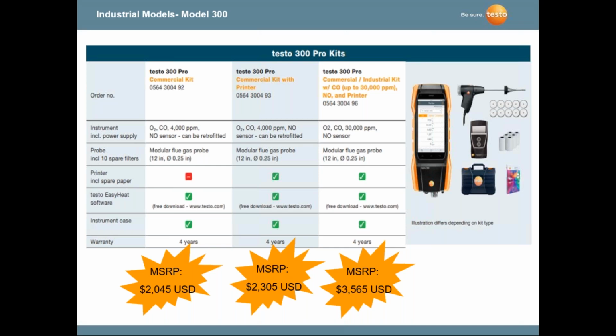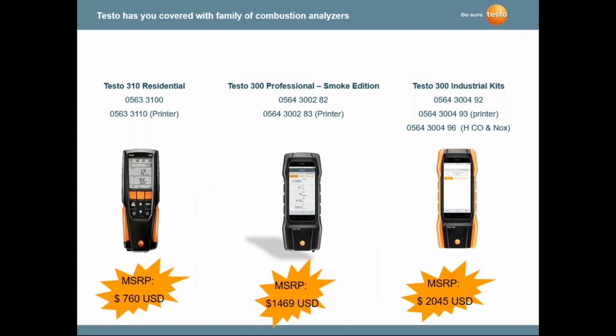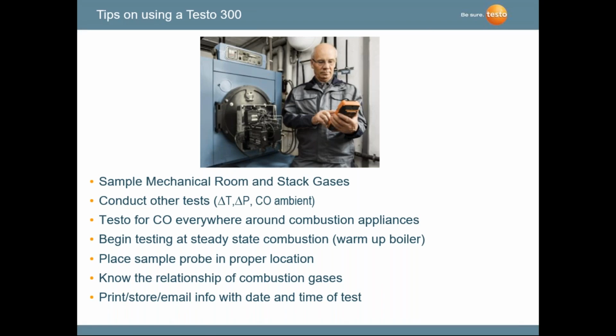So there's the lineup of the 300 combustion analyzer. Residential, which I indicated to you, is a 310, a lighter duty type instrument. Doesn't have the capability of Wi-Fi or storage, but is very good for residential oil and gas burners. Then you get into the smoke edition, which is a very common instrument because a lot of contractors, maybe like some of you, may do both residential and commercial. And then you have the higher end instrument that's for commercial and industrial applications that allows us to do the NOx measurement. Okay. Tips on a 300: sample continuously in a mechanical room and into the stack gases.